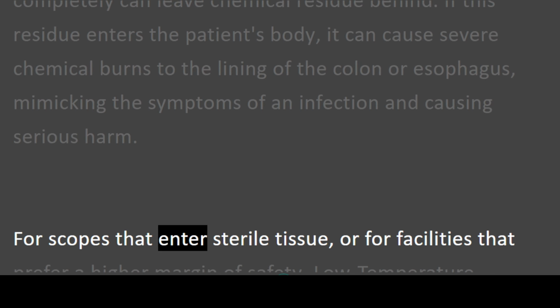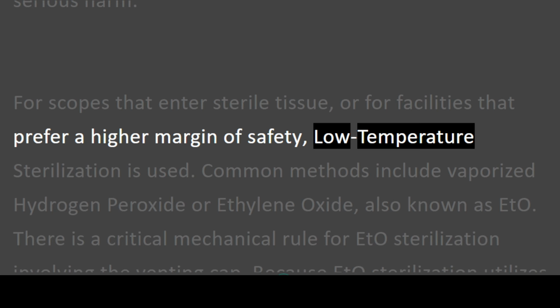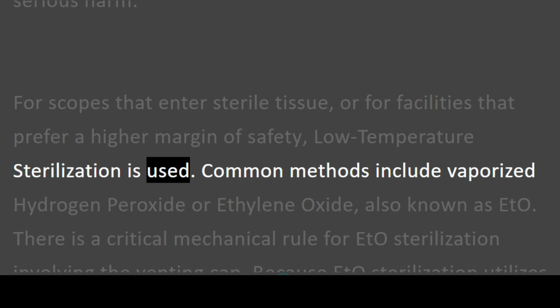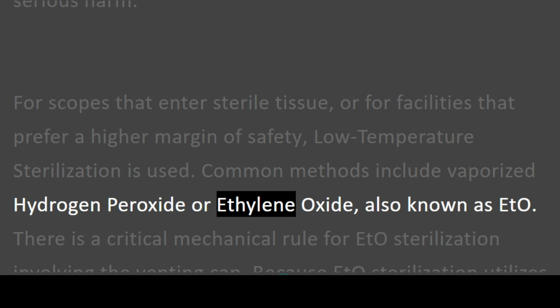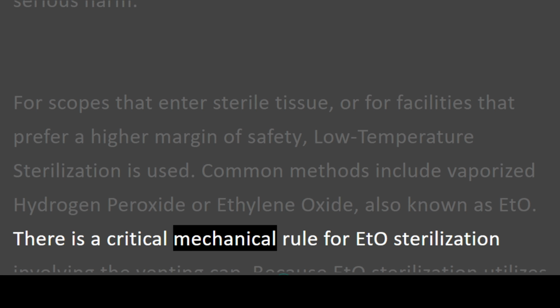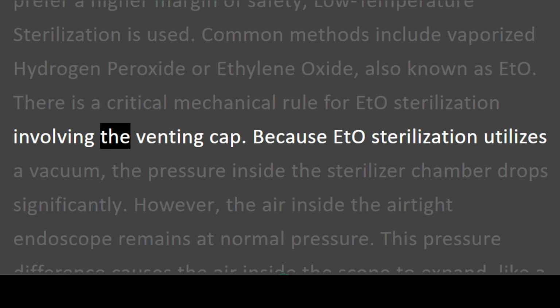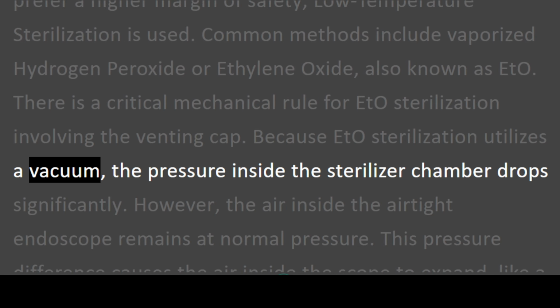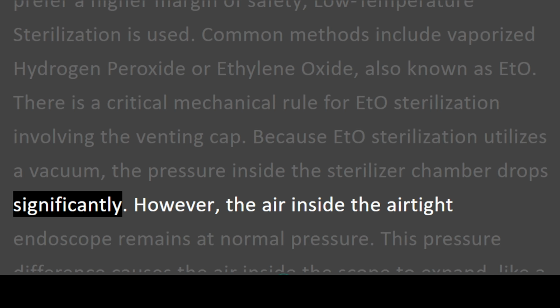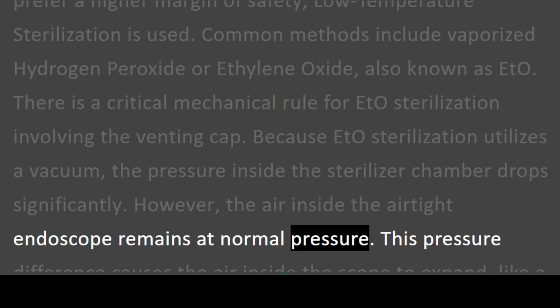For scopes that enter sterile tissue, or for facilities that prefer a higher margin of safety, low-temperature sterilization is used. Common methods include vaporized hydrogen peroxide or ethylene oxide, also known as ETO. There is a critical mechanical rule for ETO sterilization involving the venting cap. Because ETO sterilization utilizes a vacuum, the pressure inside the sterilizer chamber drops significantly. However, the air inside the airtight endoscope remains at normal pressure.